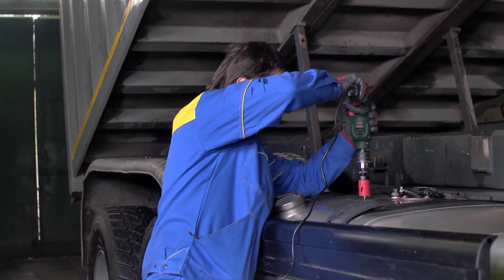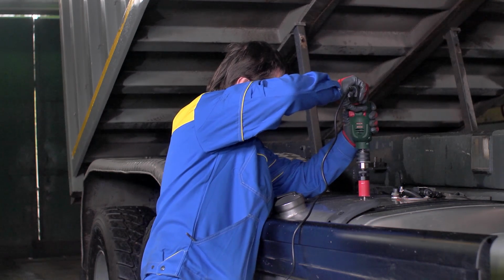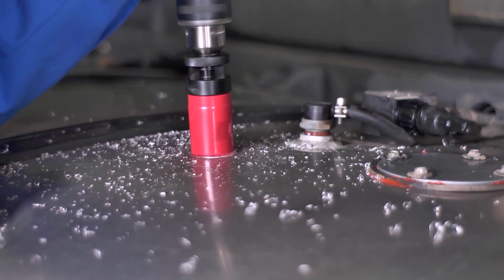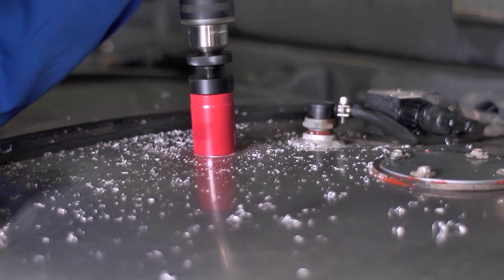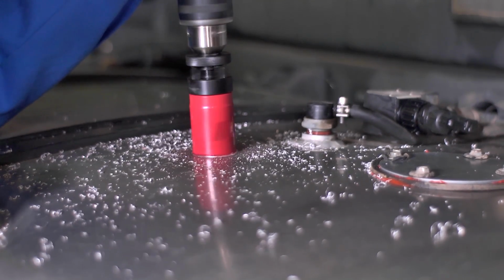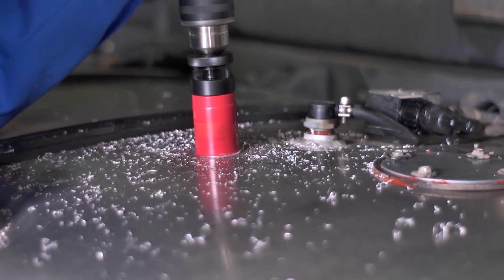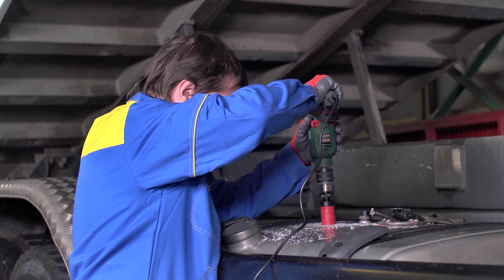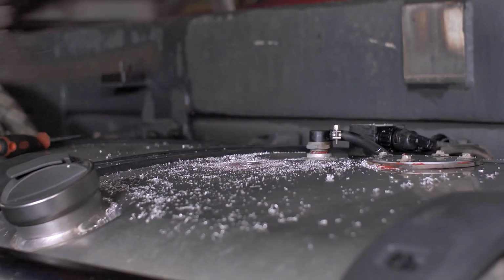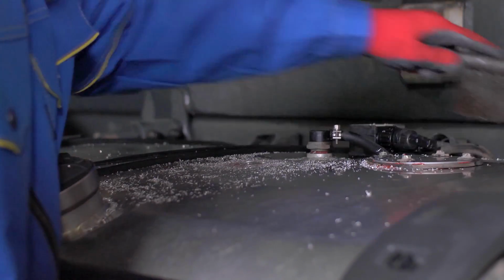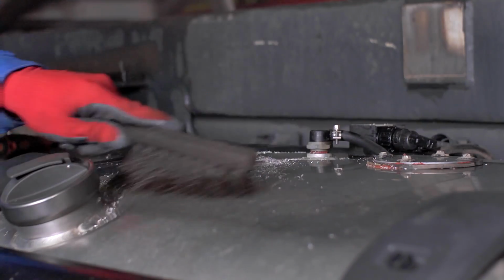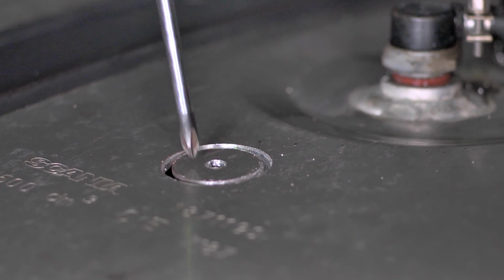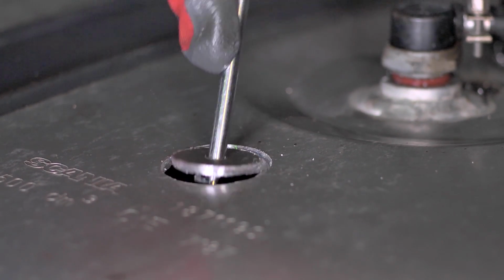The hole for installing the sensor at the chosen place should be drilled using a 35 mm diameter hole saw. Drill carefully at a slight angle. This will prevent metal chips and the cutout circle from falling inside the tank. Remove any accumulating metal chips while drilling and finish drilling the hole.